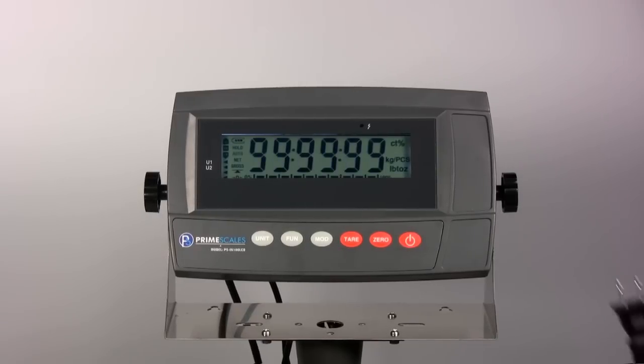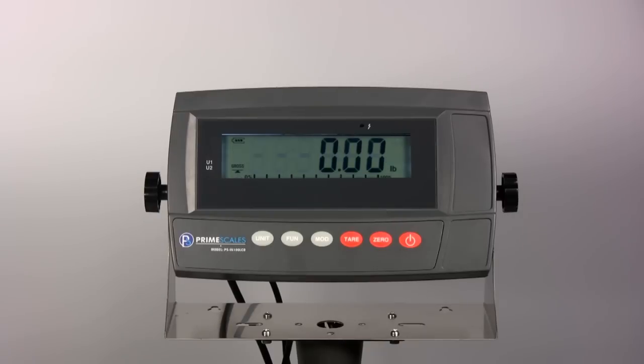It is powered by standard 110 volts AC power. It also has a built-in rechargeable battery which can run the system for 150 hours with a full charge. This indicator can be connected up to eight 350 ohm load cells.